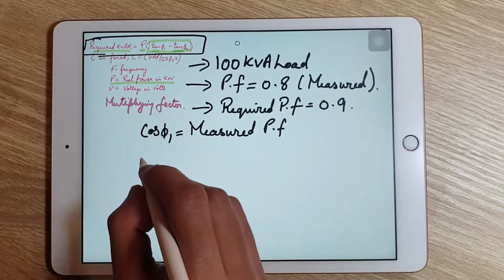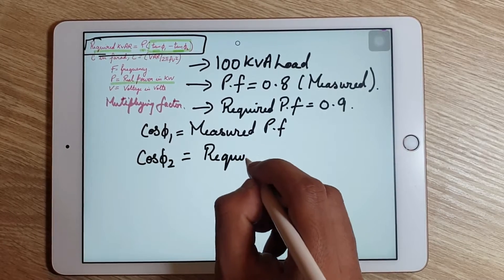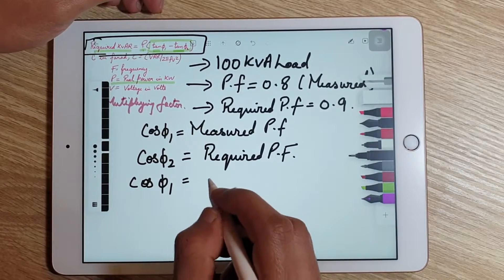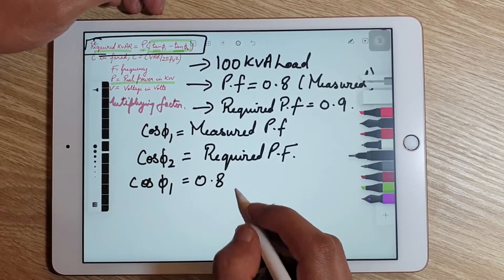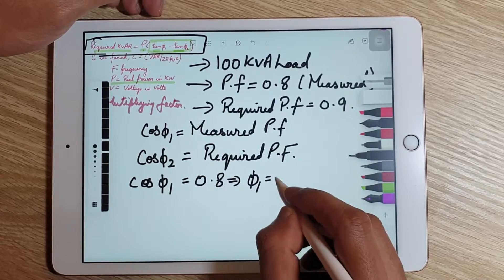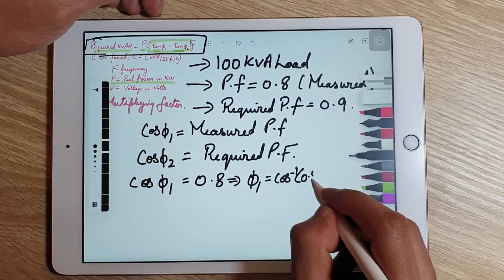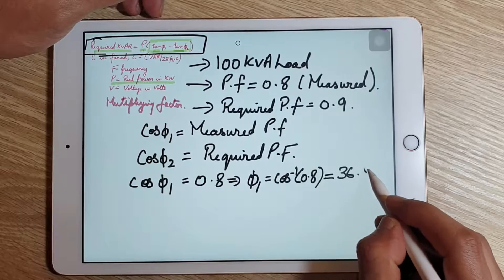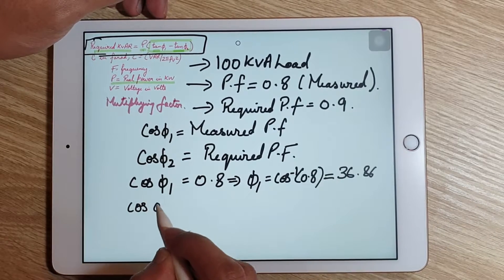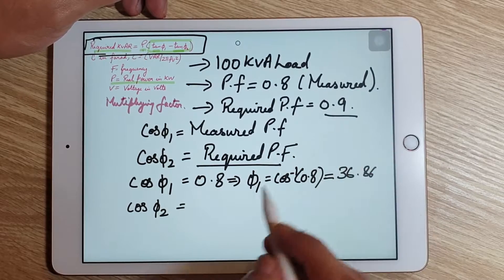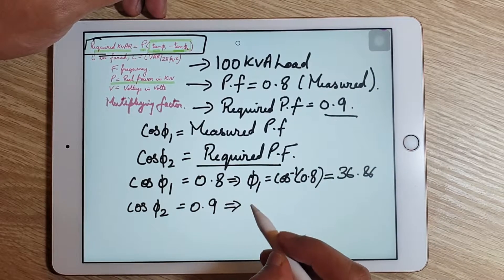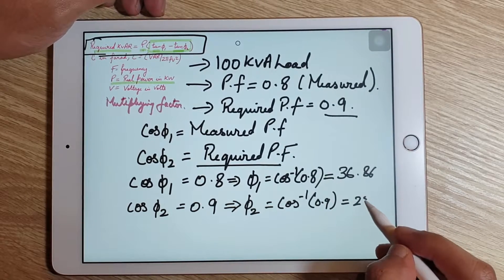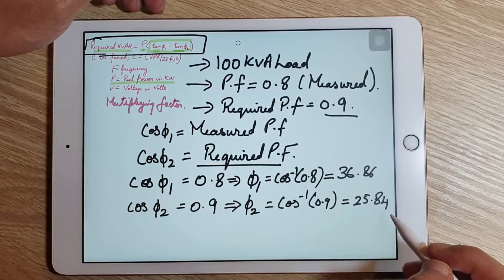We know that cos θ1 equals the measured power factor and cos θ2 equals the required power factor. Since cos θ1 is 0.8, we calculate θ1 = cos⁻¹(0.8) = 36.86°. Since cos θ2 is 0.9, we calculate θ2 = cos⁻¹(0.9) = 25.84°.